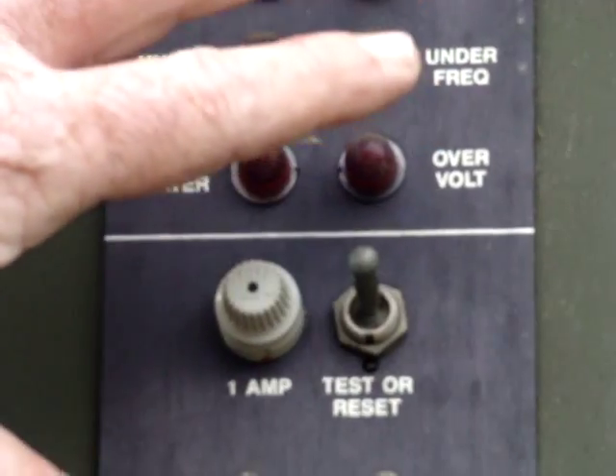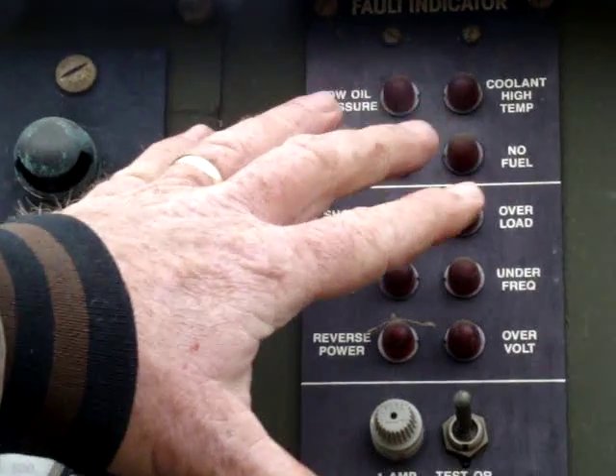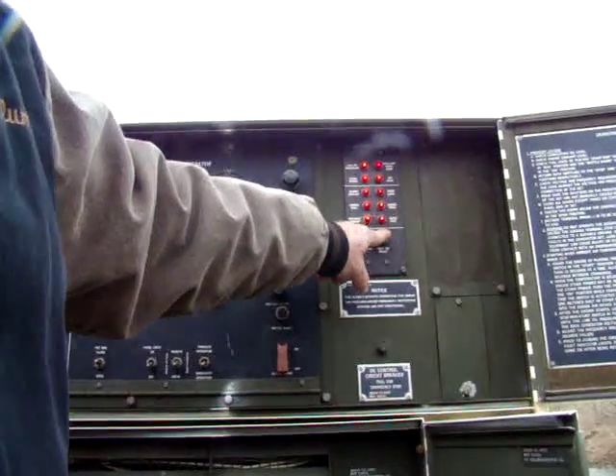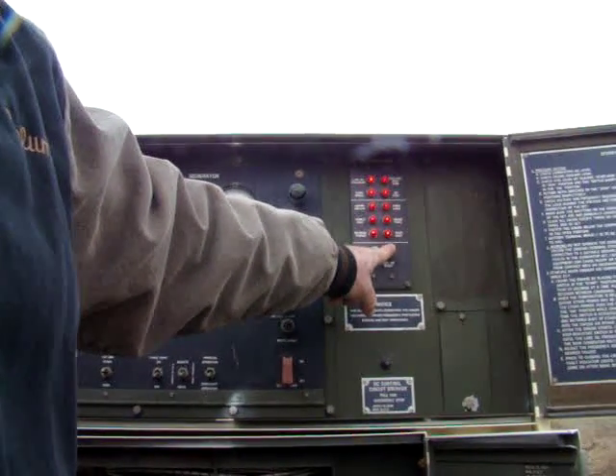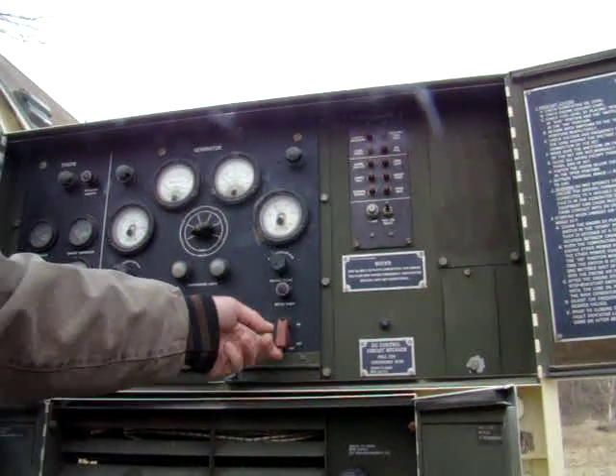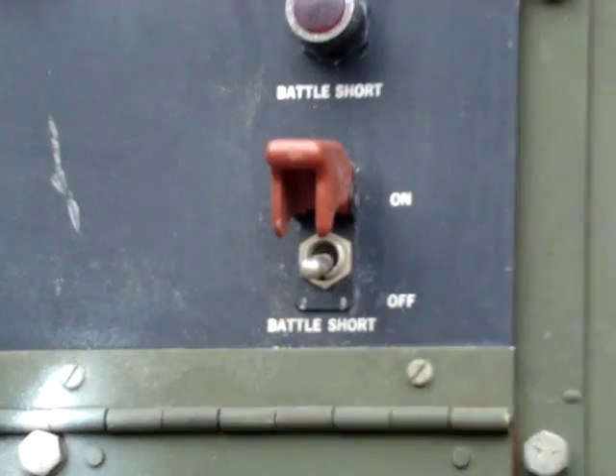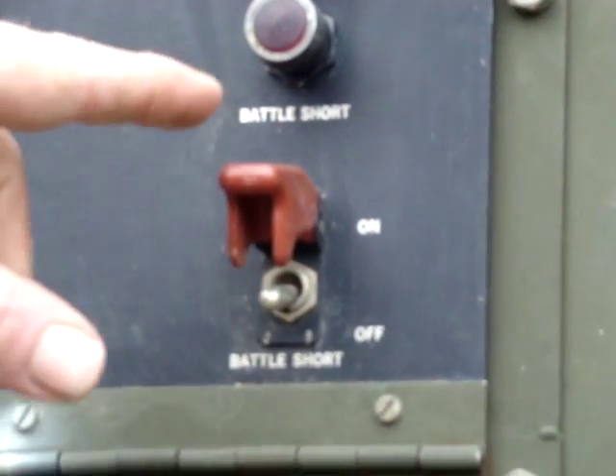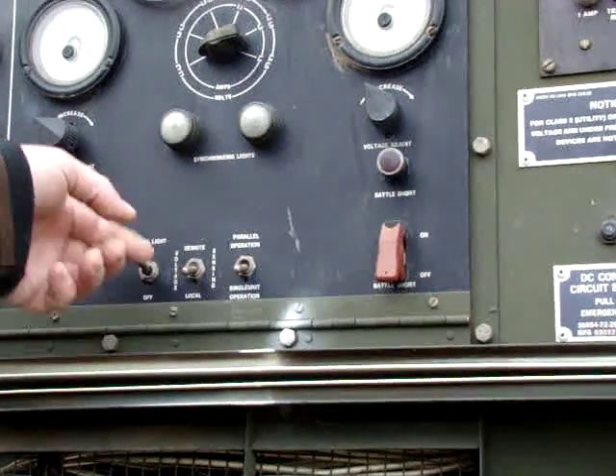The fault indicator panel — this thing is self-diagnosing to a degree; if there's a problem it'll let you know what it is. If you want to check your lights, it has a test mode so you know all your indicator lights are working. It also has a battle short switch — if the unit is damaged and would normally not generate, you can throw that switch to make it generate even if it destroys itself. In battle, that might be something you do.